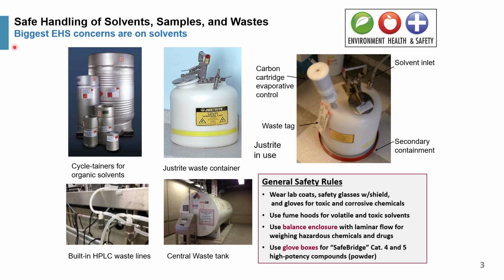On the safe handling of solvent, samples and waste, the biggest EHS concerns are solvents, particularly organic solvents. Most organic solvents are delivered in 1 gallon bottles. Some laboratories actually use the cyclotainer, which is like a beer keg using nitrogen pressure, placed adjacent to the hood for getting the organic solvent, which is primarily for reverse phase, acetonitrile or methanol.